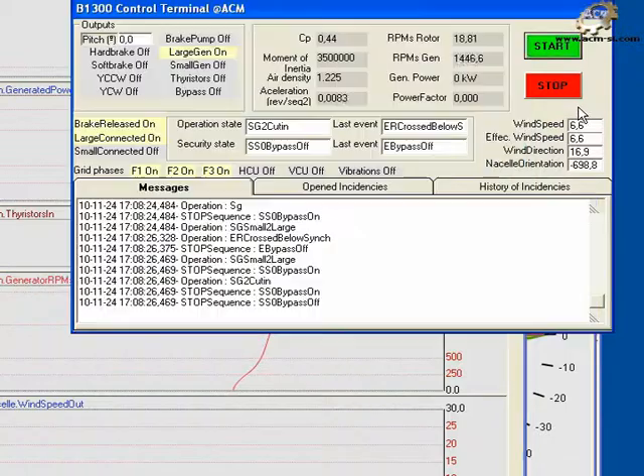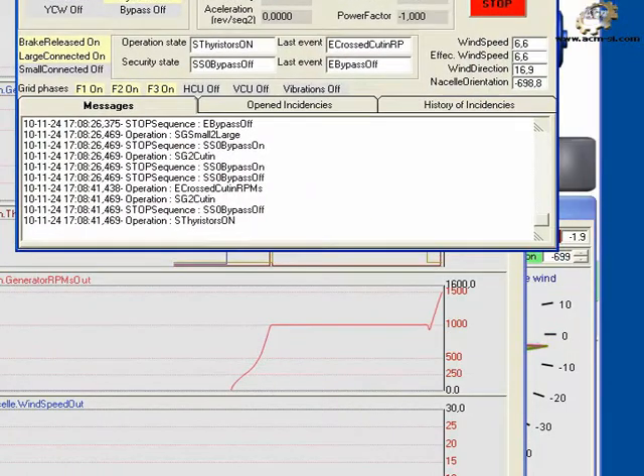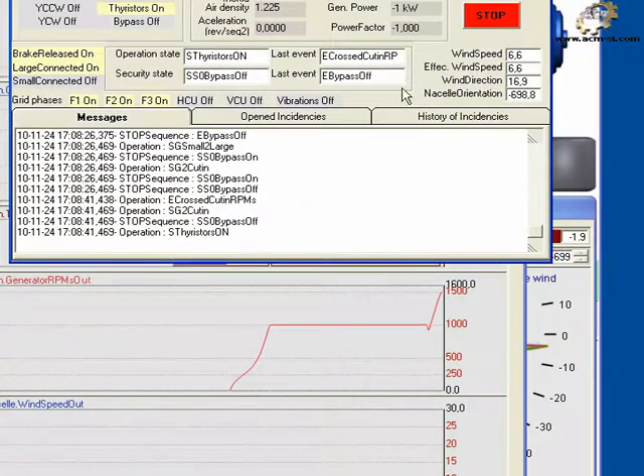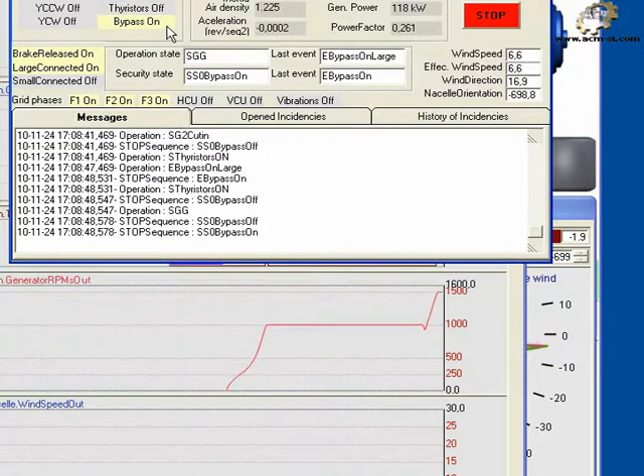In the control terminal synoptic, notice that as RPMs ramp up to 1500, or large connection synchronous speed, thyristors are on for a few seconds, and the bypass switches to on.